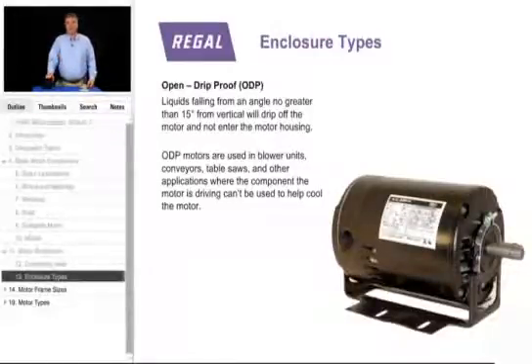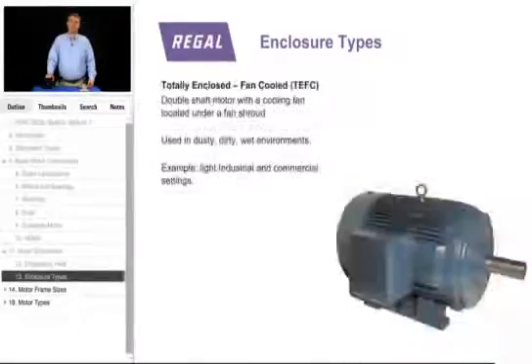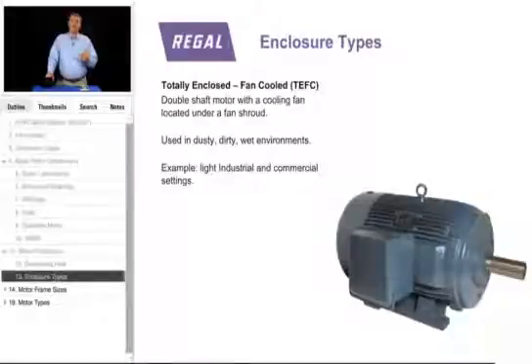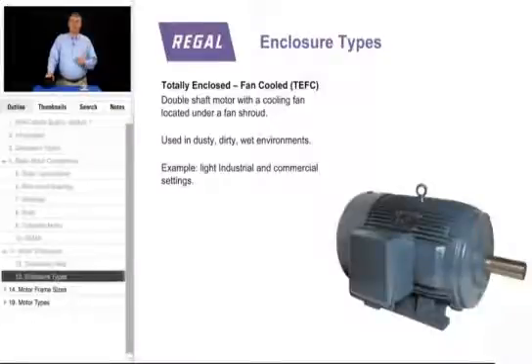The next type of motor is a totally enclosed fan cooled, or TEFC. This type of motor is really a double shaft motor with a fan on the opposite drive end to help move air over the motor and fan cool the motor. It is used in dusty, dirty, wet environments — a typical application being light industrial or commercial.